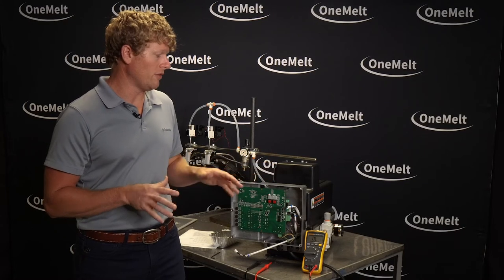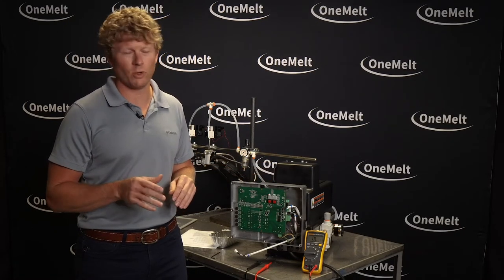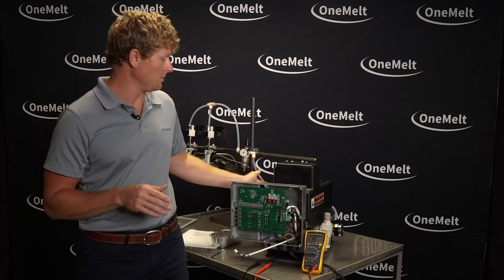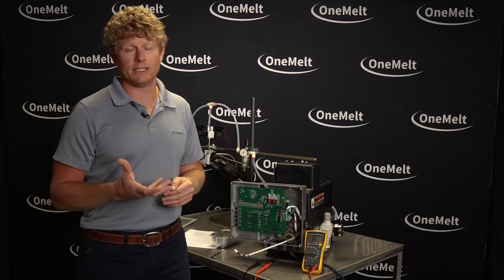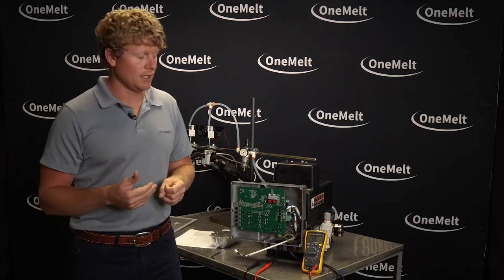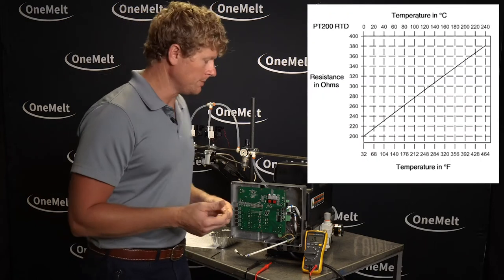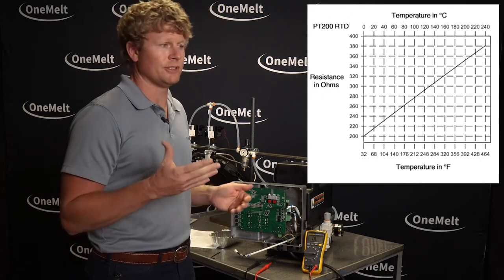The system has been off for about an hour, so it's not quite at room temperature — it's about 140 degrees F right now in the actual manifold. That matters because that's where your RTD sits and what dictates the resistance of it. This is a PT200 RTD, and at room temperature it should be in that 220 ohm range.